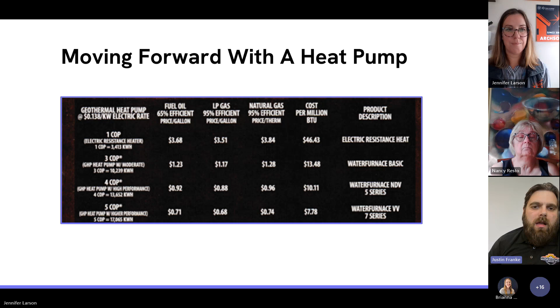And then there's also cost per million BTUs. This is just a general chart that we use to look at it. Same thing when you start looking at a COP of 5 against fuel oil - if somebody's still out there burning fuel oil, you'd have to pay under 71 cents a gallon to be more efficient than our 5 COP geothermal unit. If you take the road tax off right now, we're probably running about $2.75 for fuel oil, so that's a huge savings.